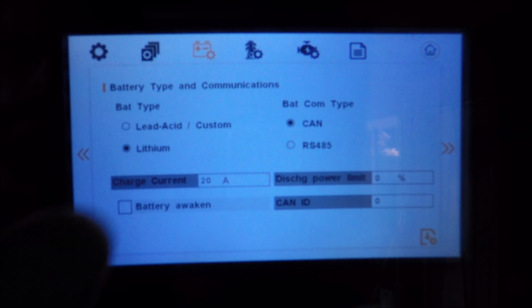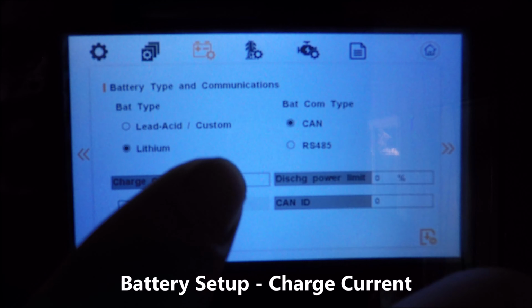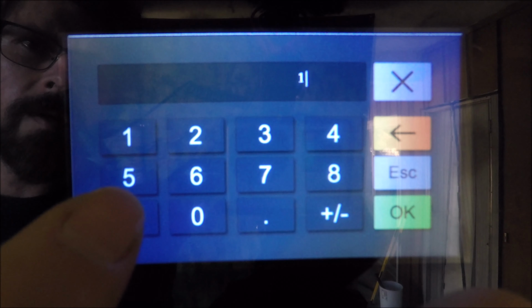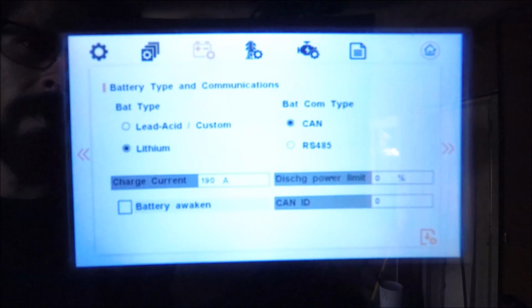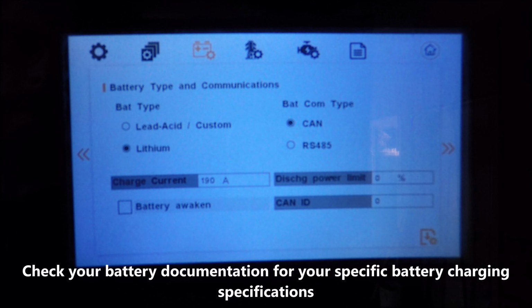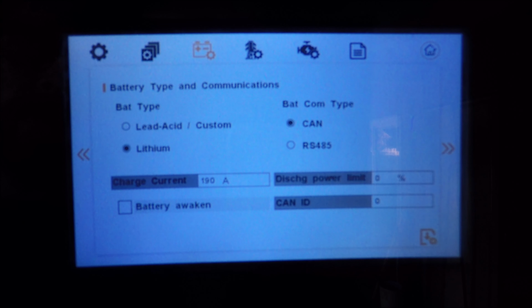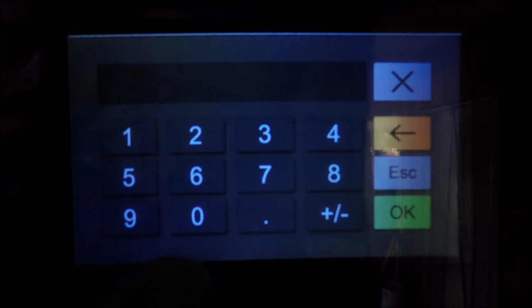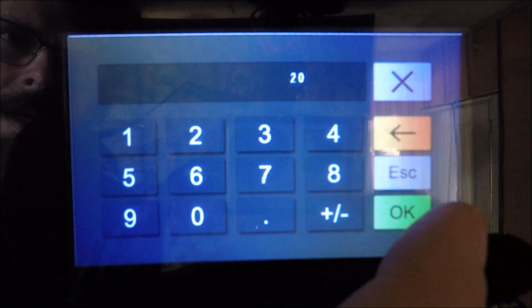We have our charge current, and we can set this up to a maximum of 190 amps. That is what is on the specification tag for these inverters, and if you set it higher, the inverter may act strange and do some strange things with charging, so make sure you do not exceed 190 amps. For me and my setup, we're going to charge at 20 amps.